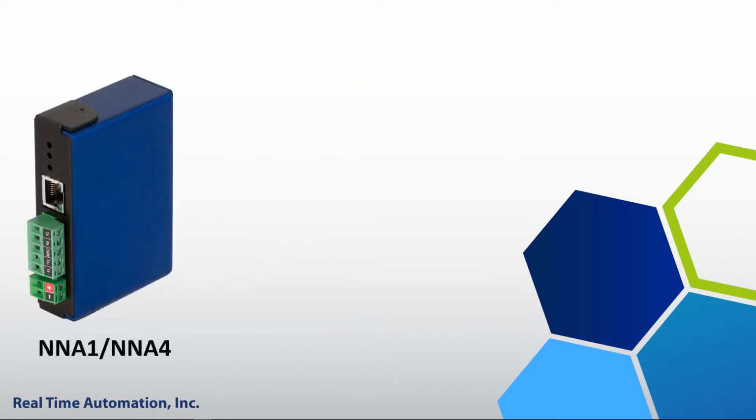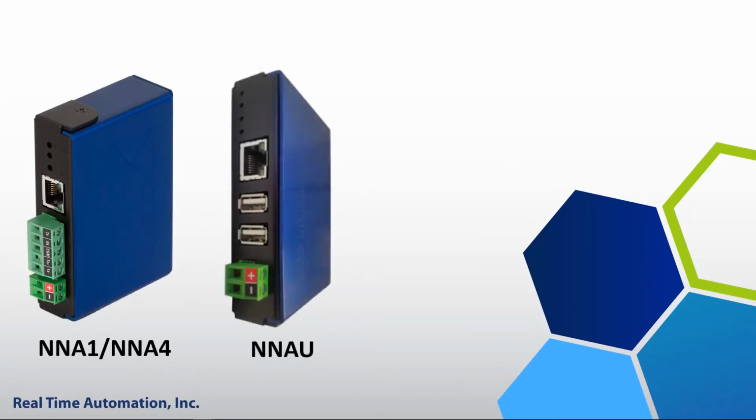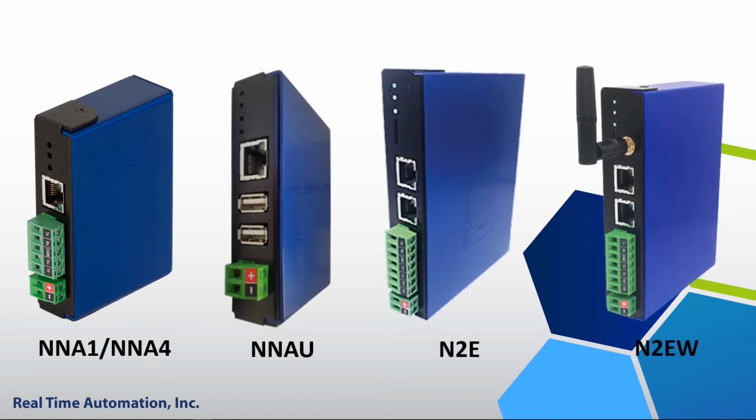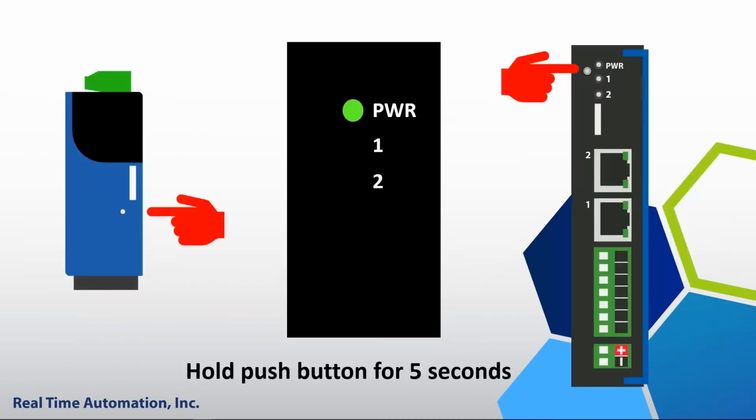If you have an NNA1, NNA4, NNAU, N2E, or N2EW hardware platform, then you can utilize the Intelligent Reset button. Insert something into the pinhole and hold for 5 seconds until LED 1 and 2 are flashing green. This means the IP address has been set back to factory default, which is DHCP.